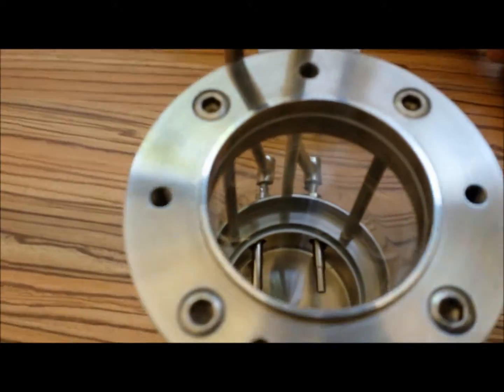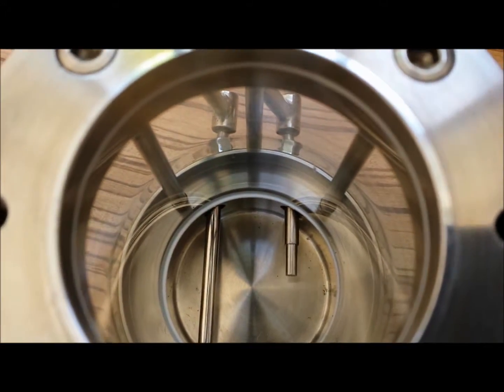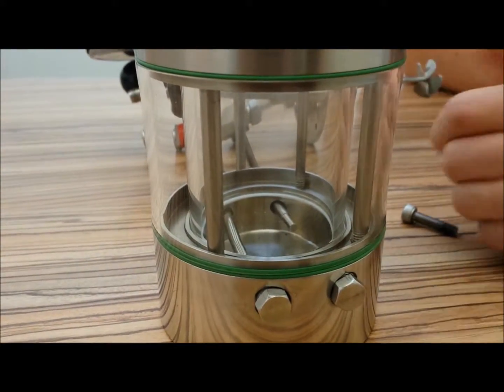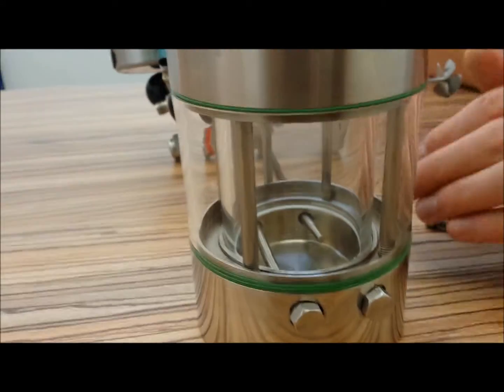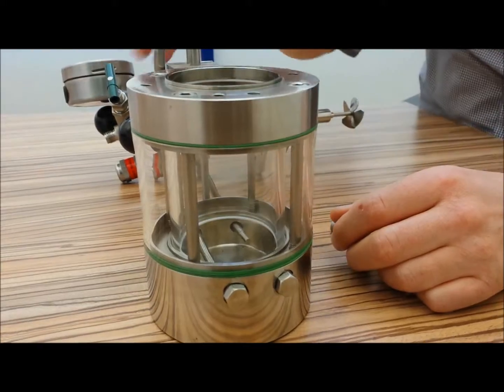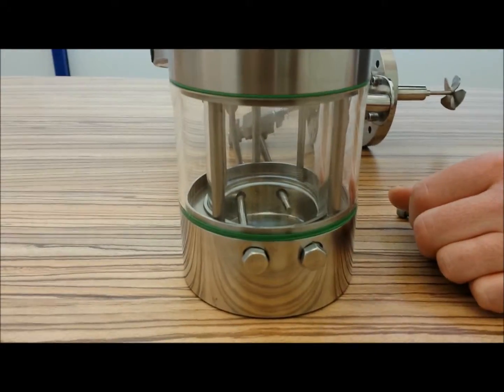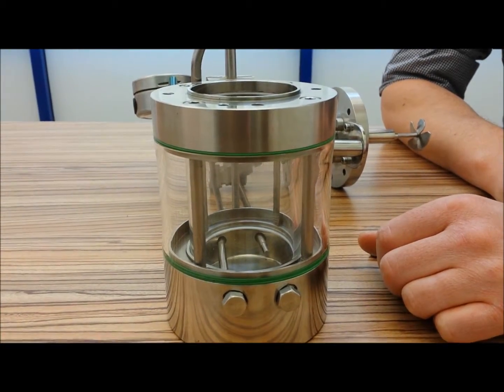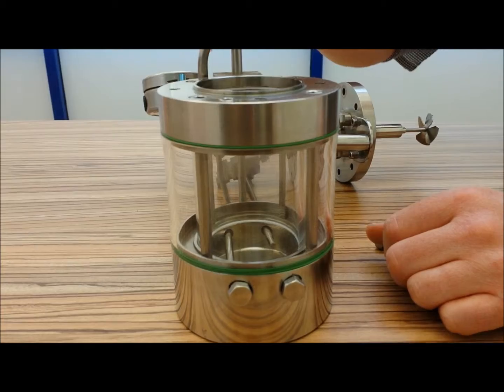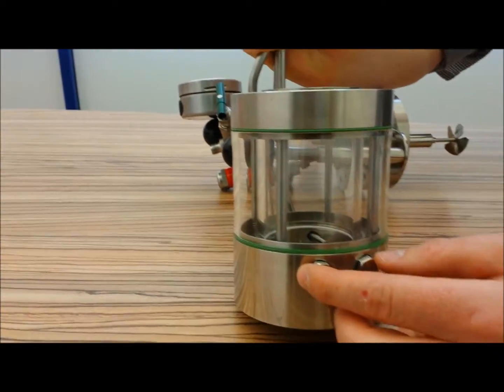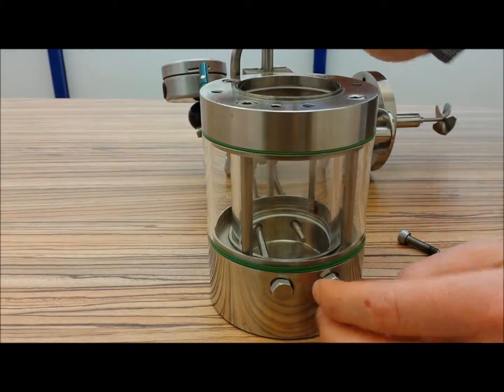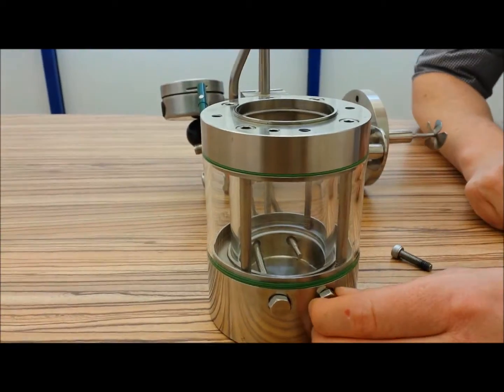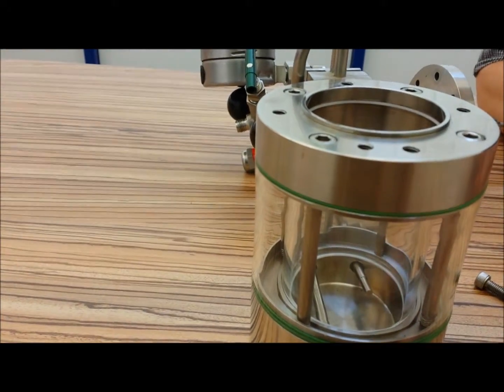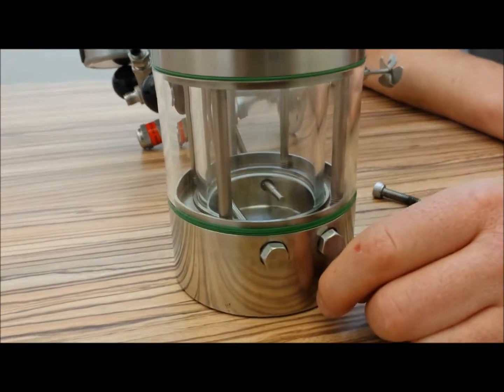What's really nice about this reactor is you only need enough volume to just cover the reactor temperature probe, which is about 10 milliliters of solvent. So you can run this calorimeter with just something like 10 milliliters of solvent. We have a 250 mil volume in here. The minimum that you need to work this reactor is about 10 mils. You'll notice there are a couple of ports here. These ports are designed to allow you to introduce material or take material from right at the bottom of the reactor. So you have the lid with ports on it, but you also have an additional 2 ports down the bottom here. So you can have up to 6 ports in this particular reactor.